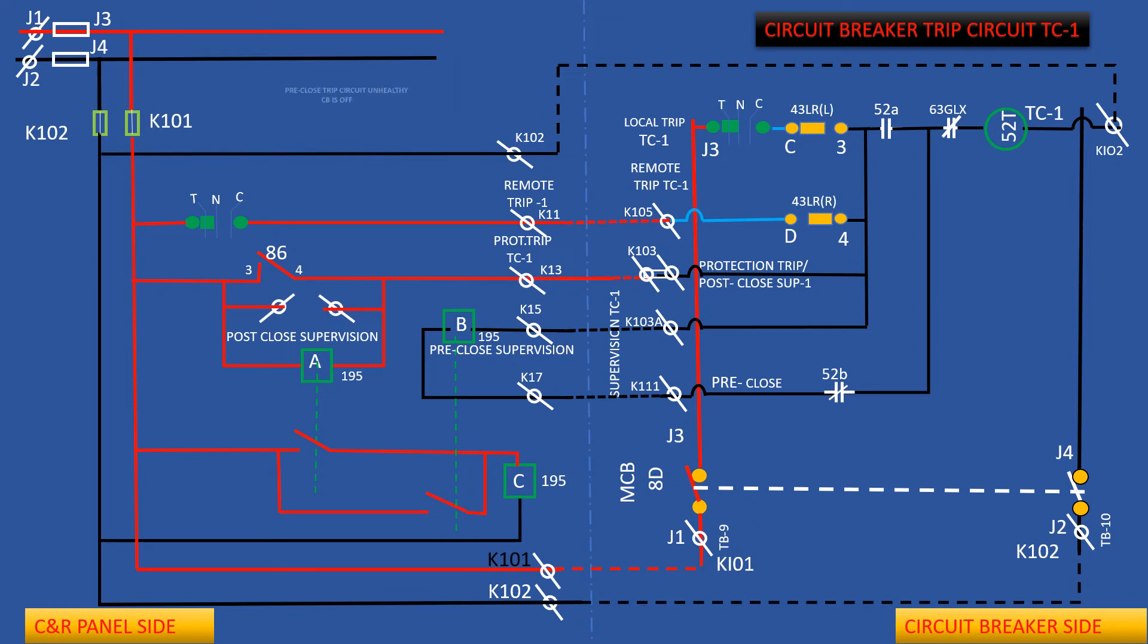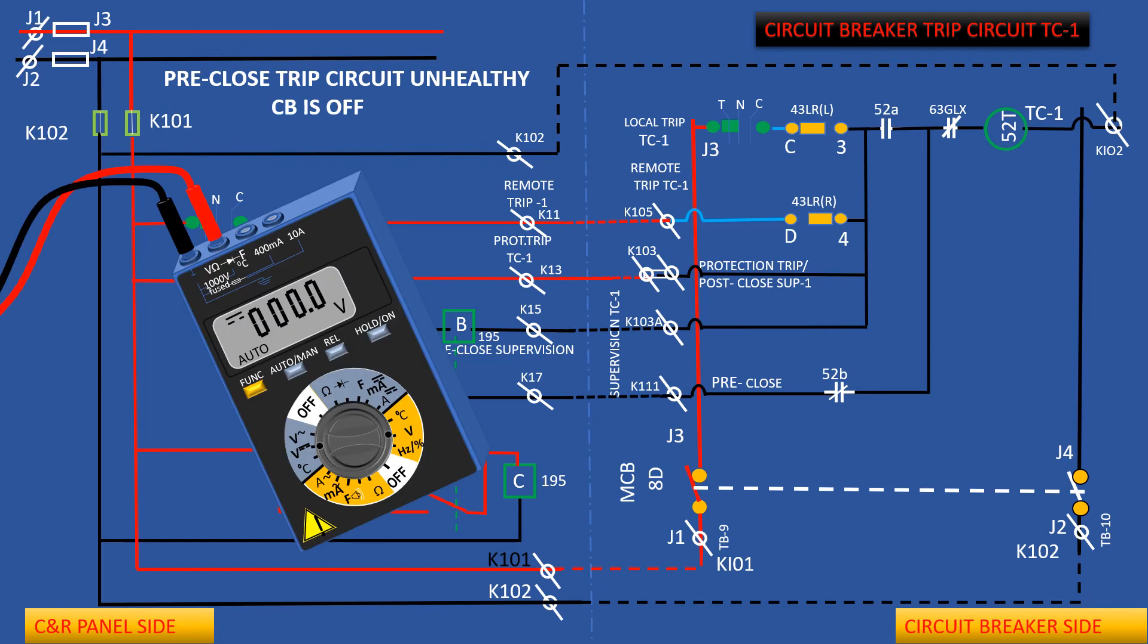Pre-close trip circuit unhealthy due to fault at trip circuit. Disconnect the connection at terminal block ferrule number, wire number K103 first. Measure voltage at each point as shown. Watch multimeter reading also.